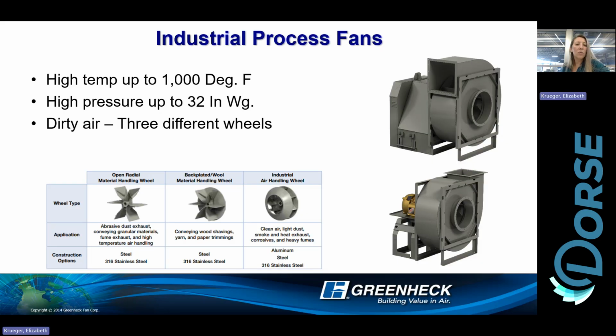Beyond that, if you have an application where you're going to see some crazy temperatures, I had one down in Arizona, a burn facility, that had to exhaust a 1,000-degree airstream. In order to do that, an industrial process fan was needed. They actually had several of them, made out of fully stainless steel, and we changed the configuration so that the motor's even farther away from the scroll. There are heat slingers.